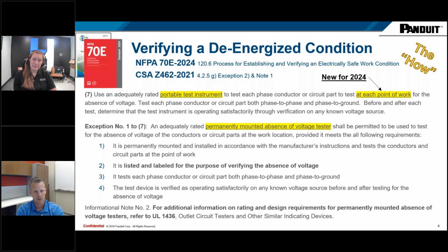And then steps 3 and 4 are more or less the bread and butter of that process. It's the automation of that step 7, right? You're testing phase to phase, phase to ground with this device, and it's got to test a known voltage source before and after. That's the core part of the process that absence of voltage testers automate. So that's the standard stuff, right?